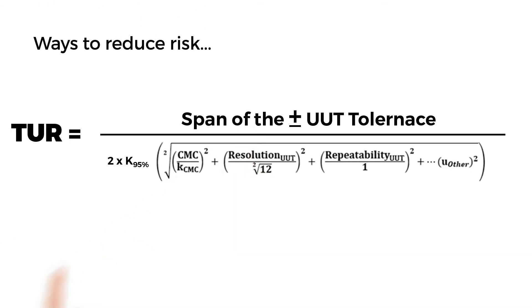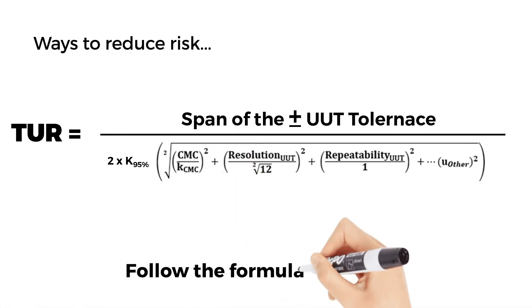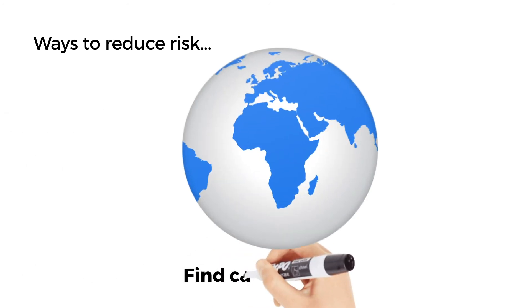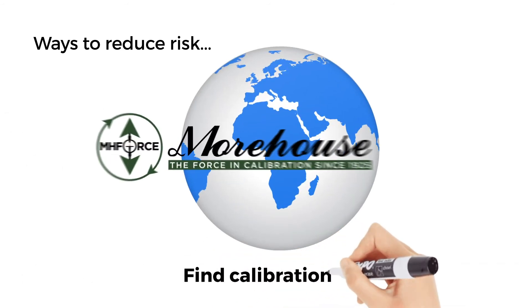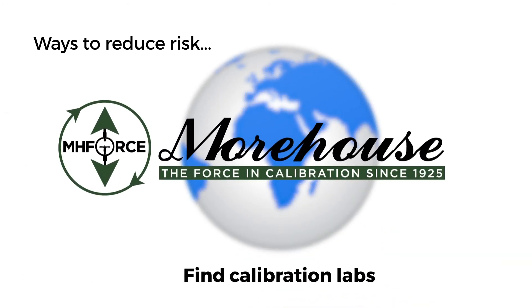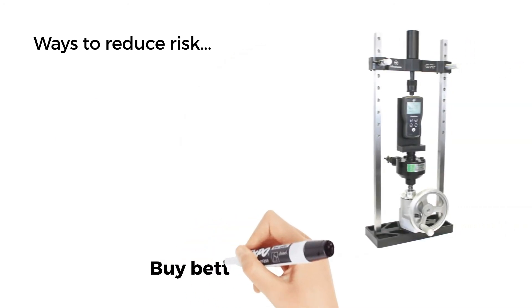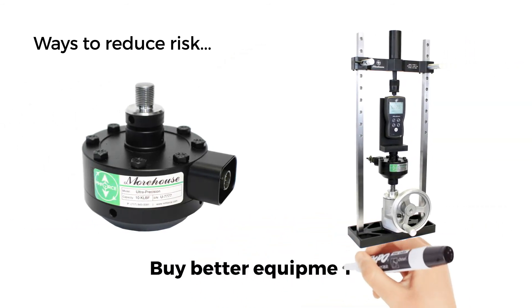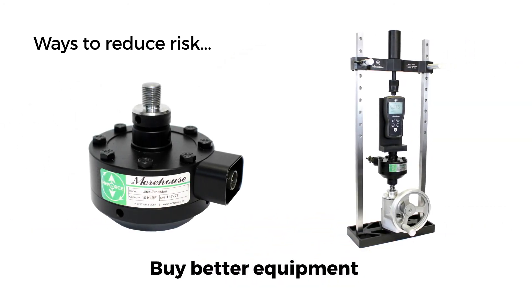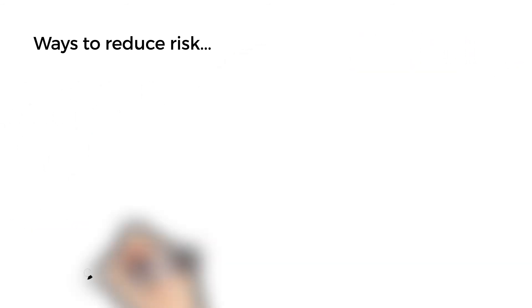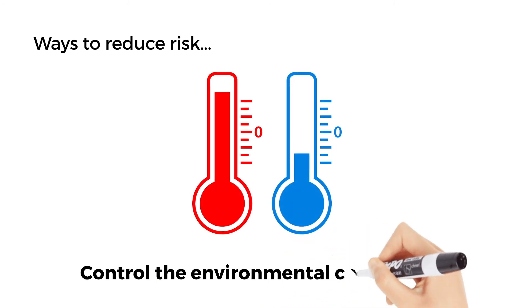The ways to reduce the risk are simple. Follow the formula for TUR. Find calibration labs such as Morehouse with the lowest measurement uncertainties. Buy better equipment that is repeatable and has enough resolution. Control the environmental conditions.